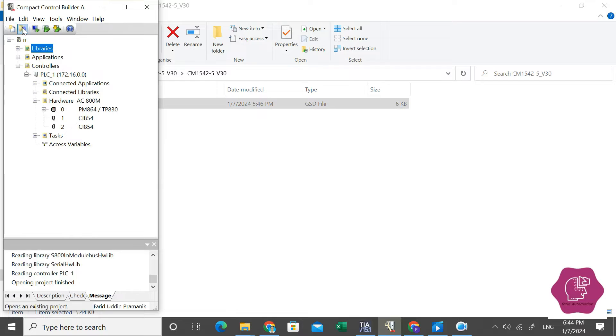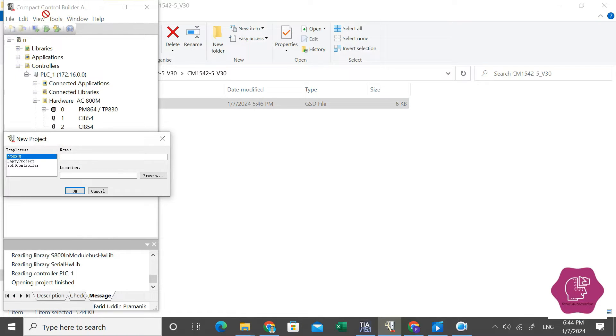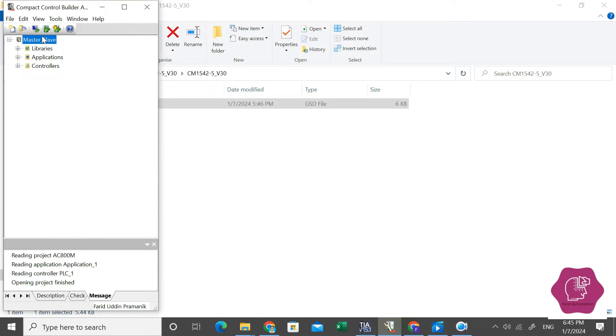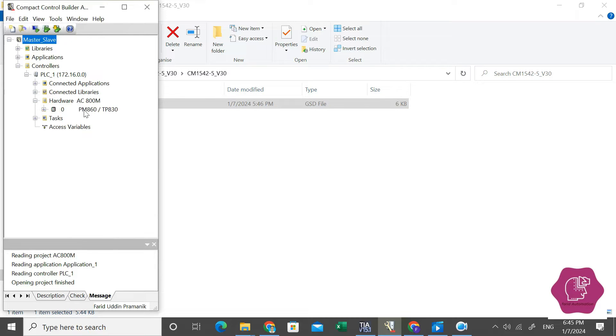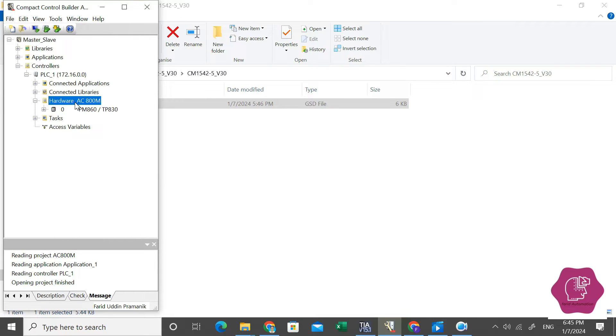Now I will create a new project in Compact Control Builder as AC800M and name it as master-slave comb. By default it has taken PM860 CPU. You have to see there is no communication module. So as I have shown, you have to add a Profibus module — that is the CI854 master module. Click hardware.